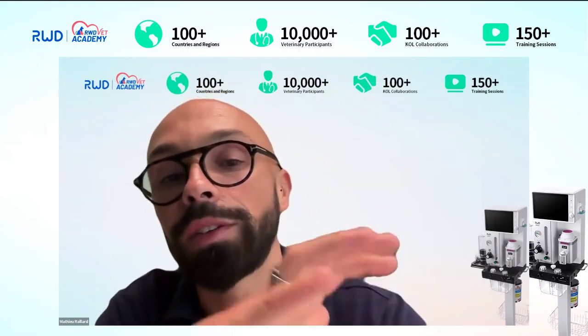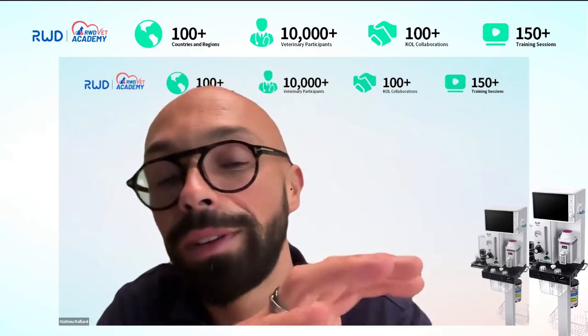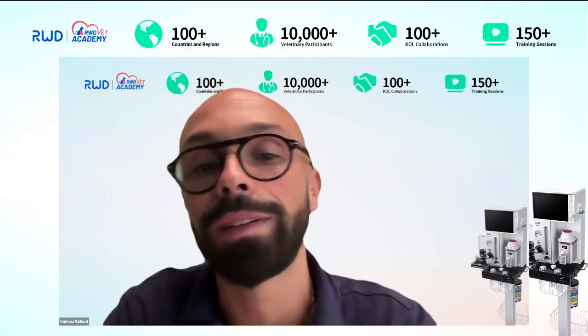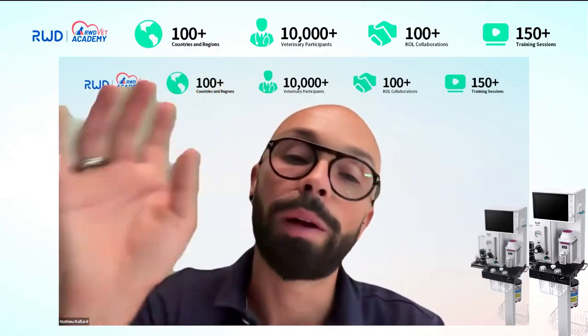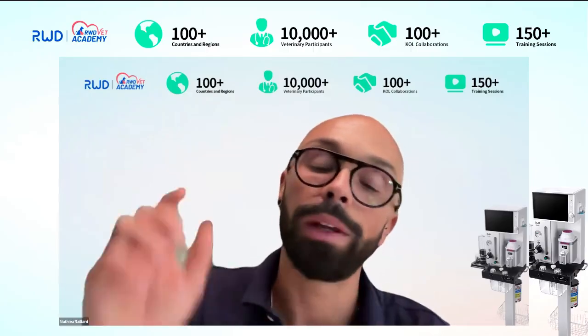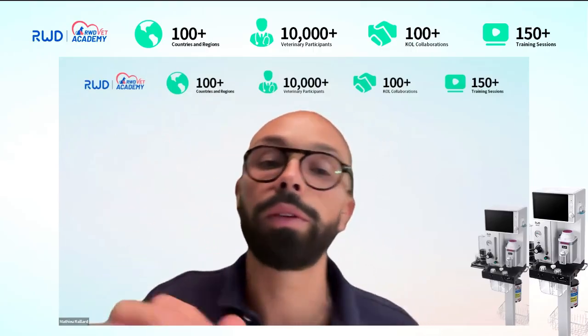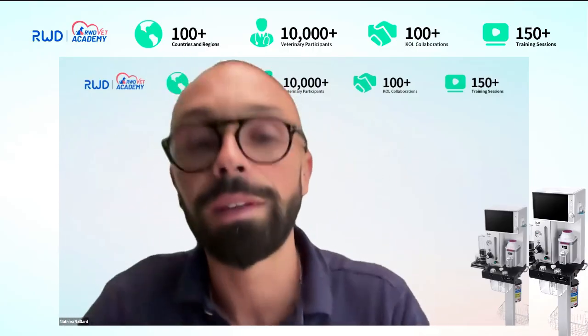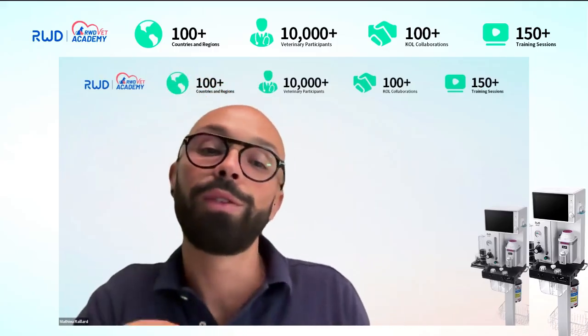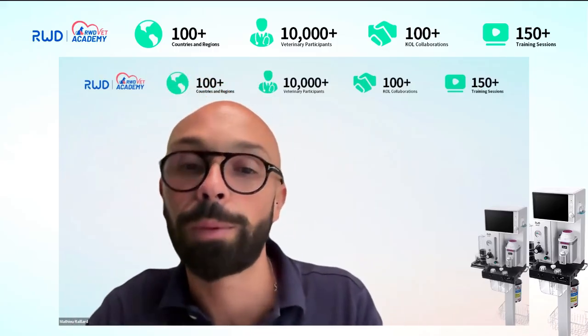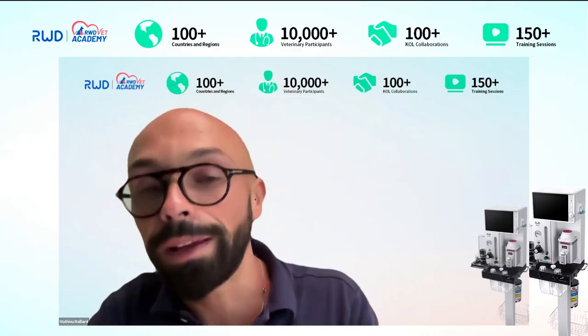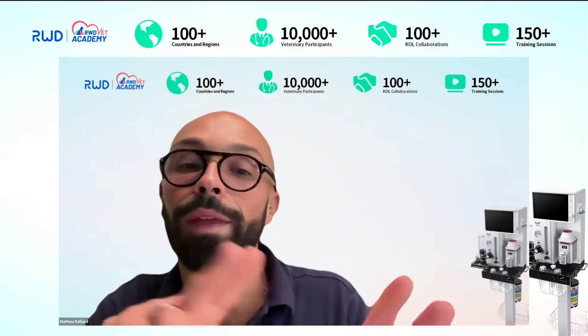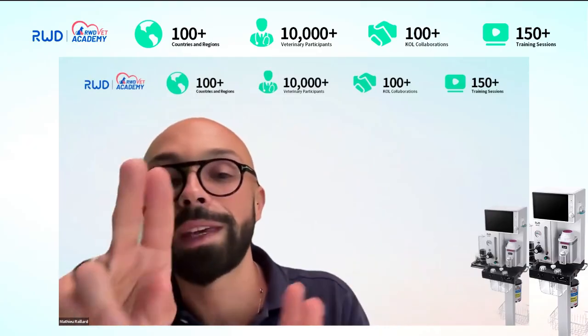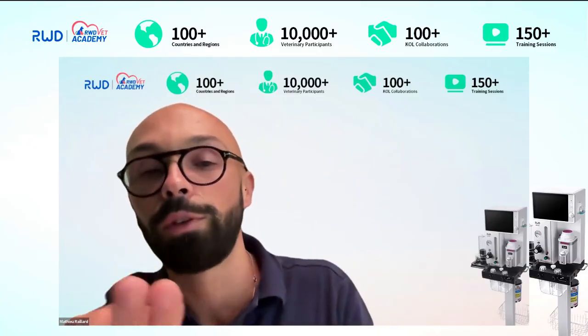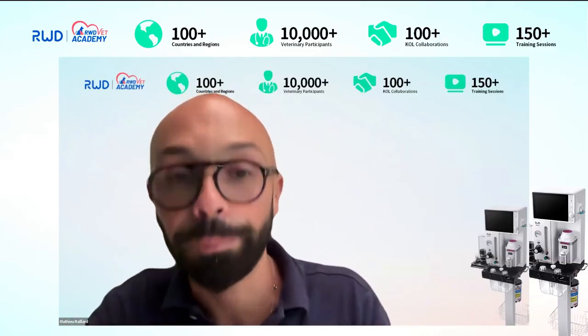The ICU ventilators and the anesthesia ventilators have very different designs. An ICU ventilator is built around having always a flow through it, and the flow can be bigger or smaller, but the way the ICU ventilator will detect a breath from the animal is a difference between inspiratory flow and expiratory flow, and that's very fast to detect. Therefore, when they detect that, they can massively increase the inspiratory flow and help very quickly.